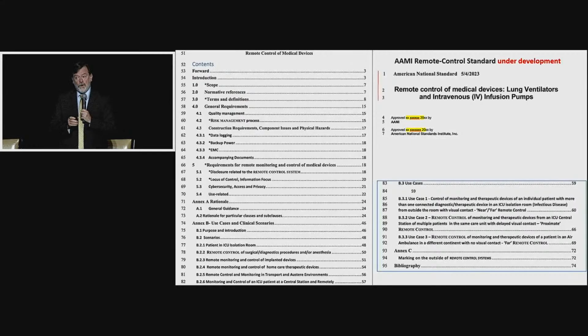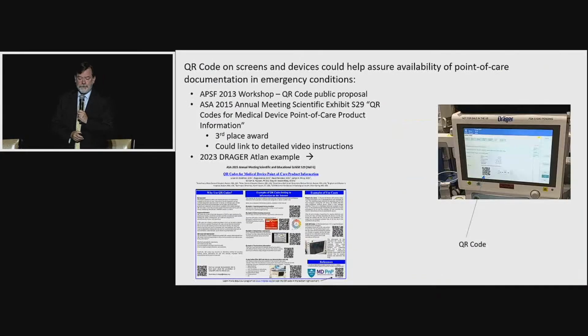We also changed the scope, so it isn't remote control of all medical devices - it's limited to ventilators and infusion pumps, in part because the emergency use guidance is going to time out this month. It actually timed out in May, but was extended to this month. So now manufacturers won't have an easy process for adding remote control to these devices, and we're trying to help with that, as is the Society for Technology and Anesthesia in support of that.